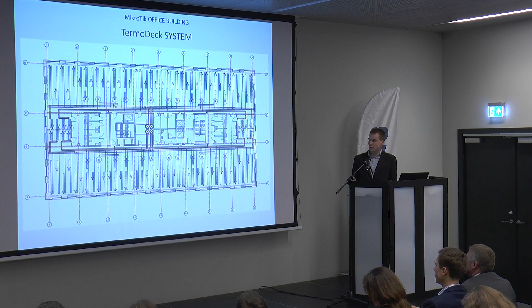But when you need to rearrange to put some smaller offices, some smaller rooms, there is a second duct for a second array of outlets, marked blue, which are normally closed for this open space layout. But if you make separate rooms inside, you can always open those outlets and have air also in those rooms. So it's very easily adjustable. You don't have to do any ductworking if you plan to divide the floor into many rooms or offices; it is actually very easy to adjust.